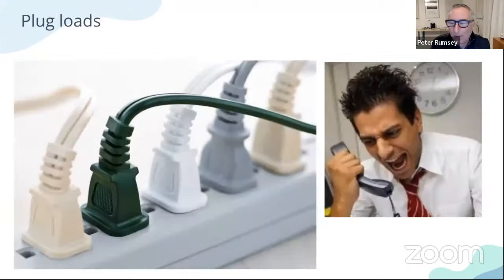Okay, so a little bit about the plug loads. I have another story for you. I remember once when I was working for a tech company a little while ago, we had measured the plug loads for computers in many of the buildings for this tech company, and we were coming up with 1 watt per square foot. That was a measured requirement for electrical. So I was saying, we're going to design the cooling system for 1.5 watts per square foot, because, who knows, they might get a little bit more in there.